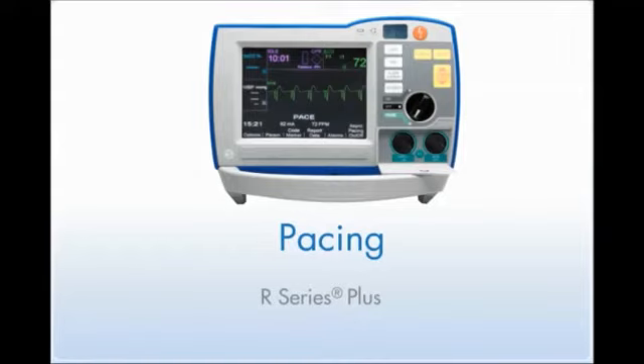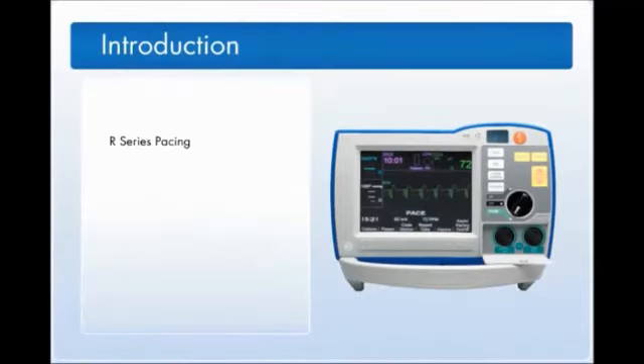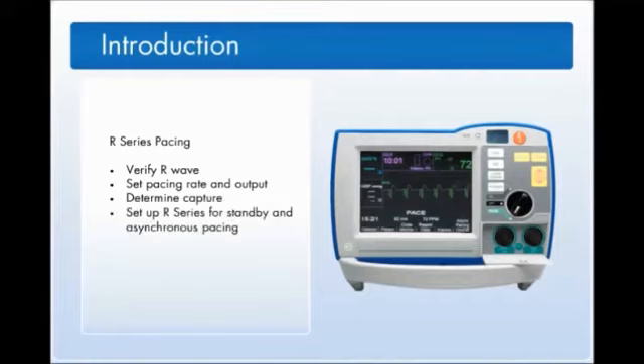Welcome to the R-Series pacing module. The R-Series defibrillator contains a VVI demand pacemaker, a safe and effective design for non-invasive temporary pacemakers. In this module, you will learn how to verify proper R-wave detection, how to set proper pacing rate and output, how to determine capture electrically and mechanically, and how to set up the R-Series for standby and asynchronous pacing.